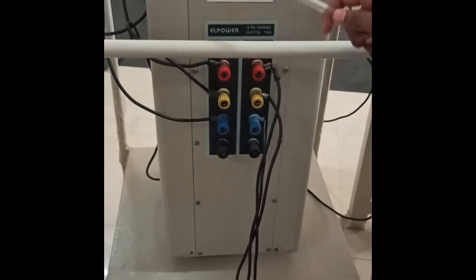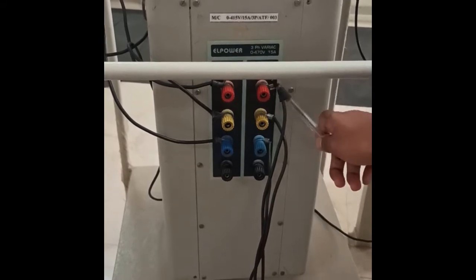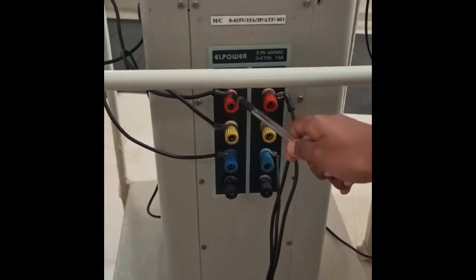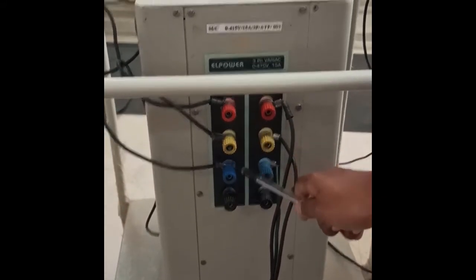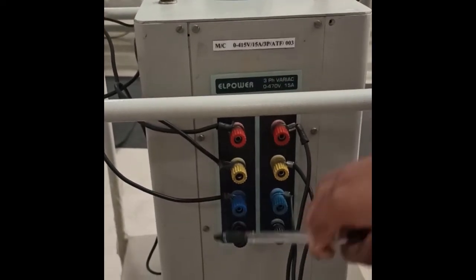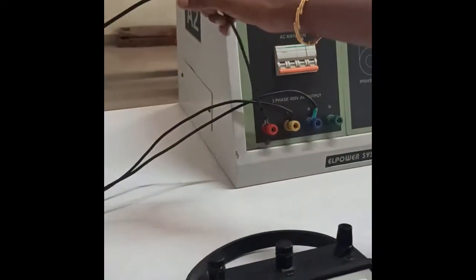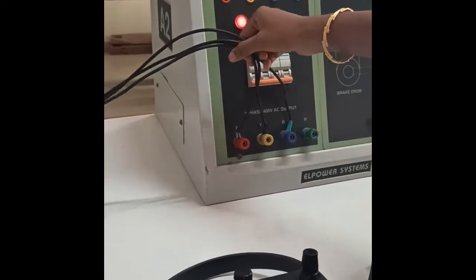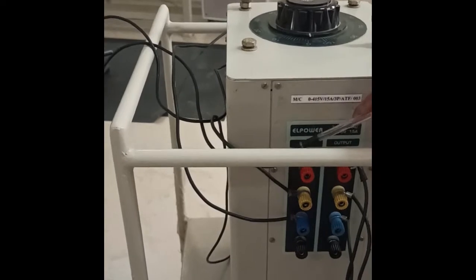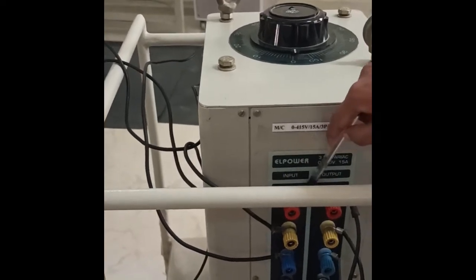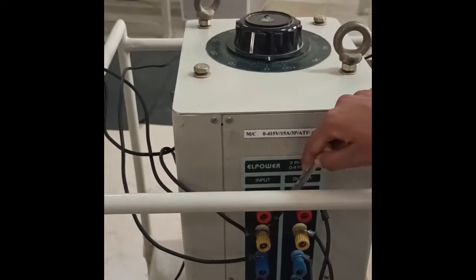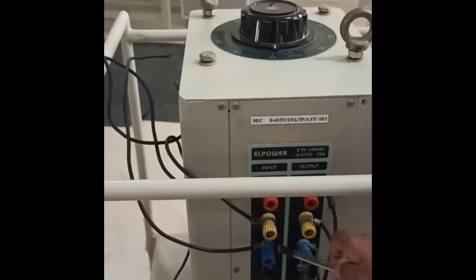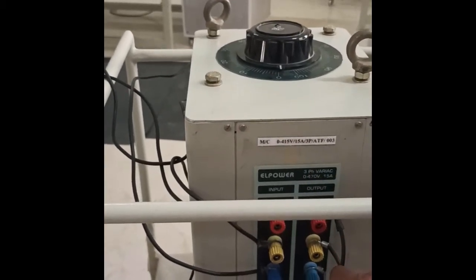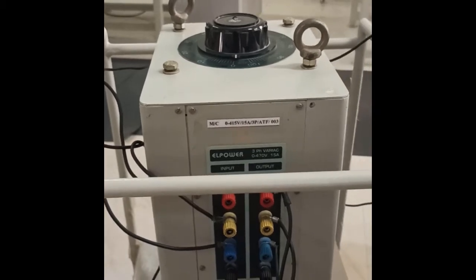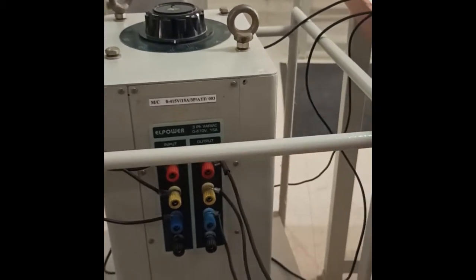Now this is a three-phase auto transformer where we have 3 input terminals and 3 output terminals. So to all these input terminals we have to bring the supply R, Y, B points. You can see here, R, Y, B from the panel supply is brought to the input terminals of the auto transformer. So R phase from the supply should be connected to the input R of the auto transformer, Y should be connected to input Y of the auto transformer. Similarly, B from the supply should be connected to the B phase of the auto transformer. The next connection we will start from the output terminals.